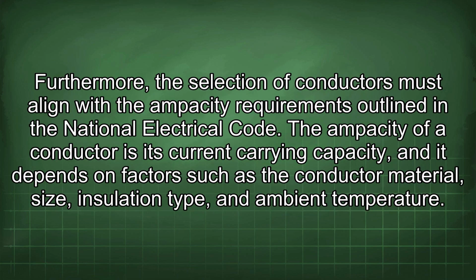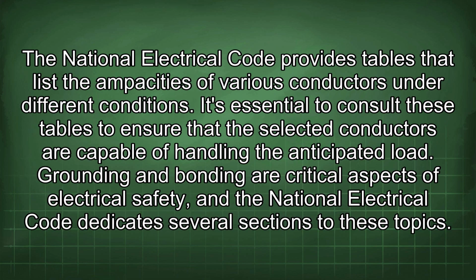Furthermore, the selection of conductors must align with the ampacity requirements outlined in the National Electrical Code. The ampacity of a conductor is its current carrying capacity, and it depends on factors such as the conductor material, size, insulation type, and ambient temperature. The National Electrical Code provides tables that list the ampacities of various conductors under different conditions. It's essential to consult these tables to ensure that the selected conductors are capable of handling the anticipated load.